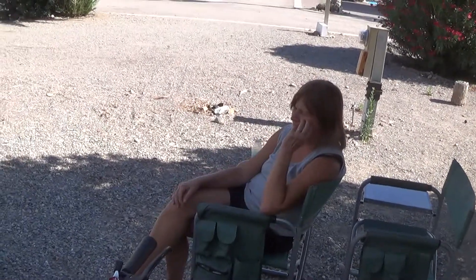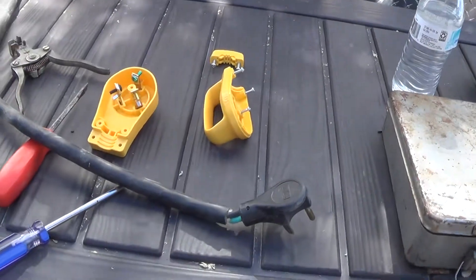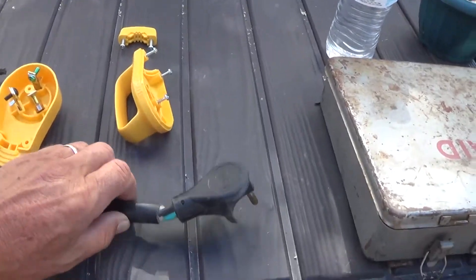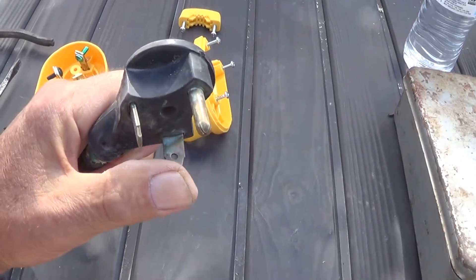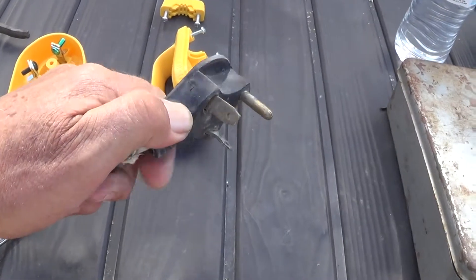It's Tuesday, May 30th, 2017, 8:51 a.m. We're getting ready to change the shore power plug on our shoreline. This is what we've had since we bought it, and you can see all the green patina starting on this one. It's arcing — the other ones don't have that.